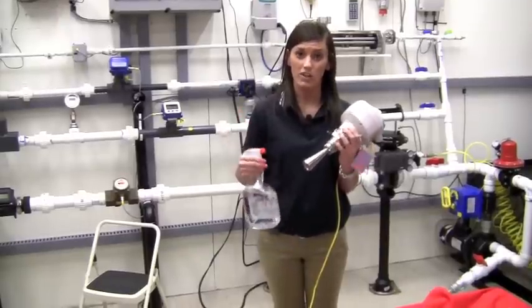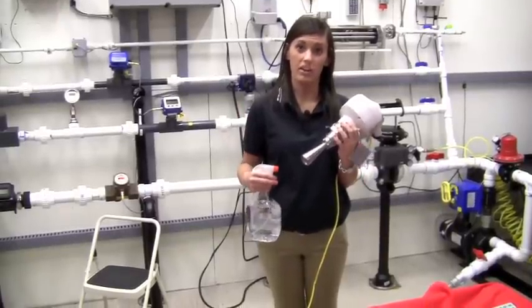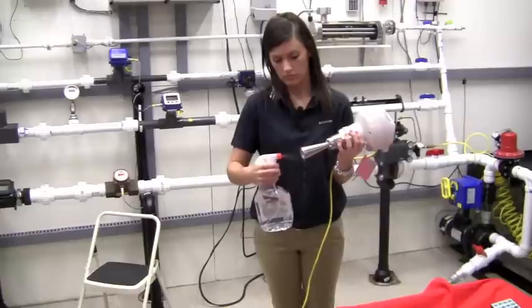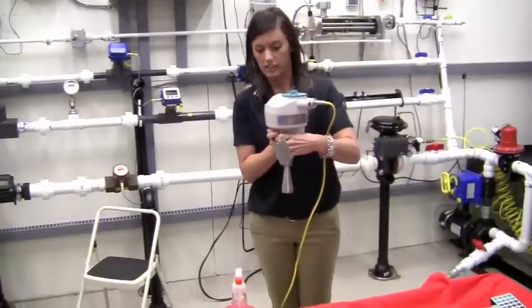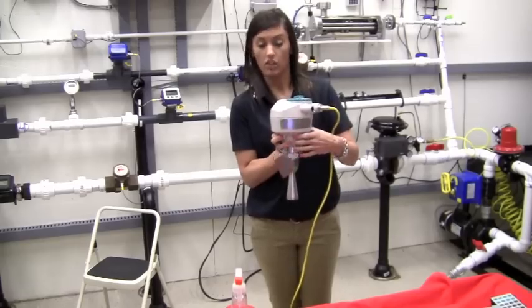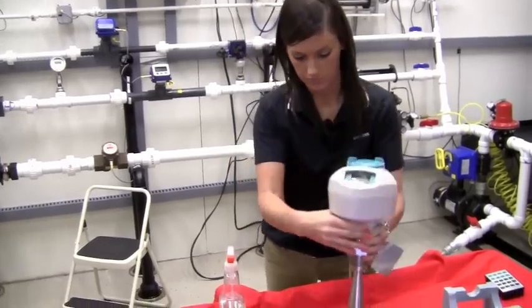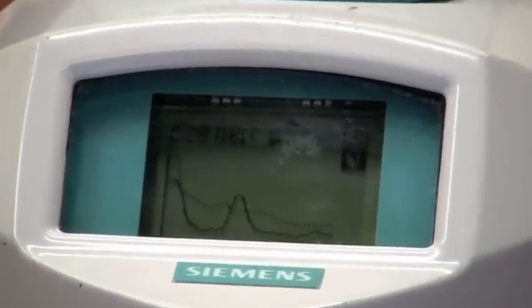Now I'm going to spray water on the inside of the horn to represent condensation buildup. Now we're going to take a level measurement and look at the echo profile. You can see how the dynamic threshold moves up so that the condensation does not affect the signal.